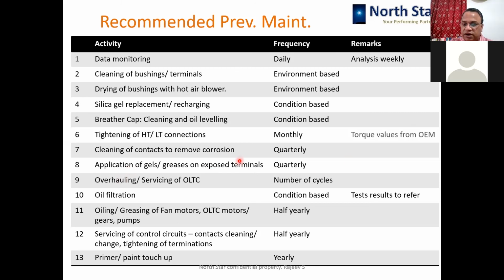Oil filtration, again condition based, I would say condition based, not time based. And only after seeing the test results that the values are deteriorating, then only the filtration should be done, else it should not be done.